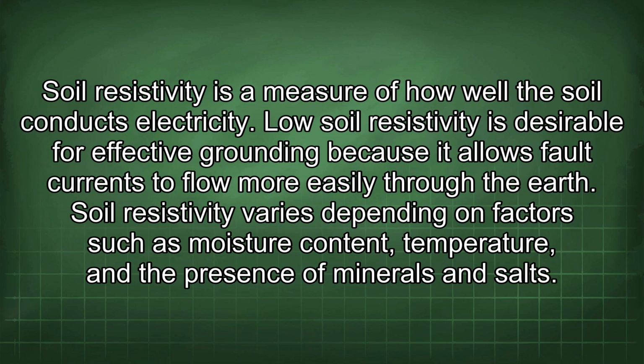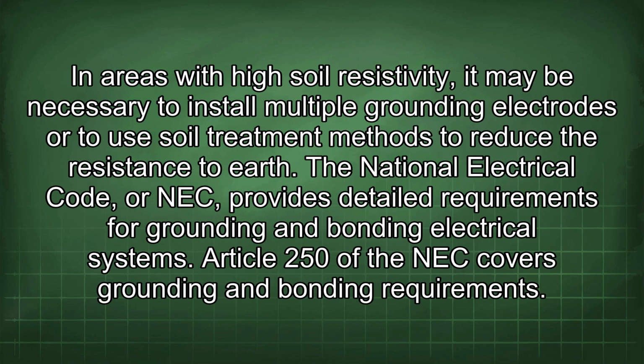Soil resistivity is a measure of how well the soil conducts electricity. Low soil resistivity is desirable for effective grounding because it allows fault currents to flow more easily through the earth. Soil resistivity varies depending on factors such as moisture content, temperature, and the presence of minerals and salts. In areas with high soil resistivity, it may be necessary to install multiple grounding electrodes or to use soil treatment methods to reduce the resistance to earth.